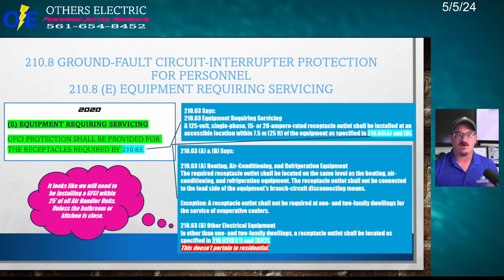Okay? Now, I know what you're thinking. Does that mean I need to add GFCIs to my air handlers? Maybe. If your air handler's in the attic, yes, you got to have a GFCI in the attic within 25 foot of it. Okay? If your air handler's in, let's say, the hallway of the house, more than likely you're going to have a GFCI somewhere because, we're going to keep reading here. So a receptacle outlet, there's an exception. A receptacle outlet shall not be required at 1 and 2 family dwellings for the service of evaporative coolers. Okay, we don't really install evaporative coolers, so that doesn't apply. But there's going to be another code.